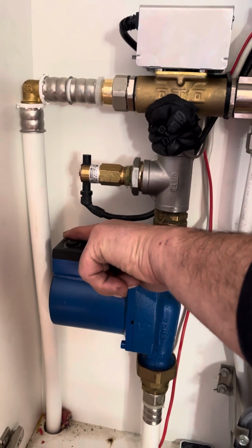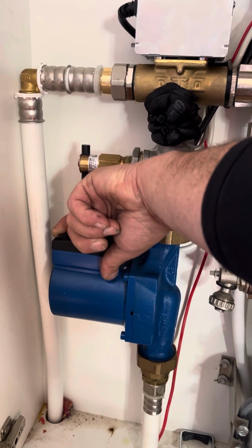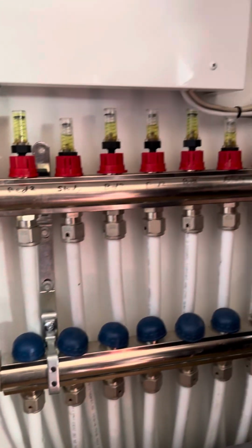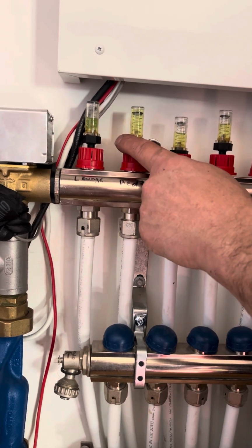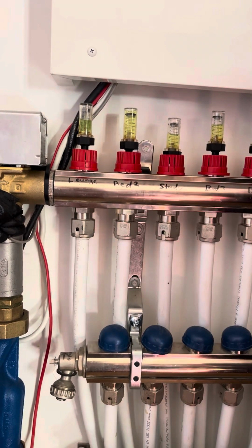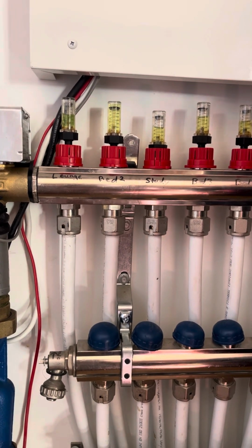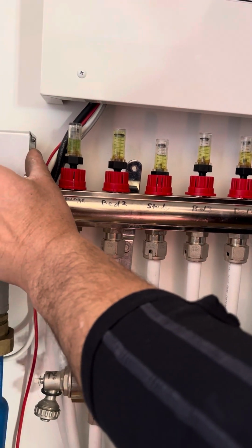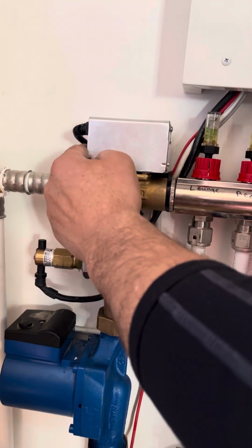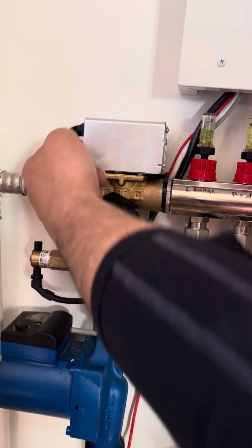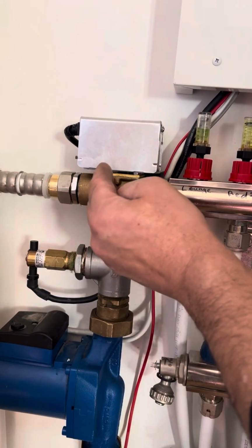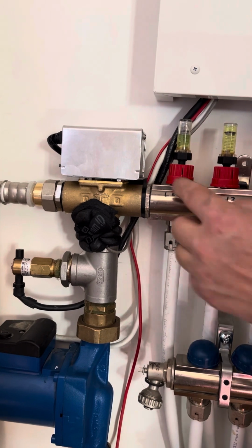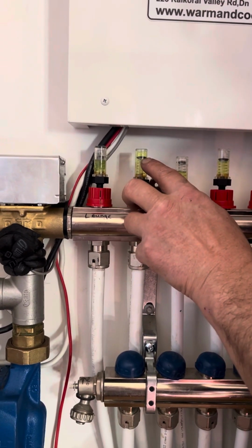You've got a pump speed control here, which is high, medium and low, but we generally want to be on high because you've got so many zones running. And you've got wee flow indicators here, which are, once it turns off hot water, it'll go to the heating mode, and this is the new valve which was installed. It's currently on hot water at the moment, so that wee toggle will move back across, so it closes to the hot water cylinder, and then the water will start flowing this way now, which we can see it's just done.